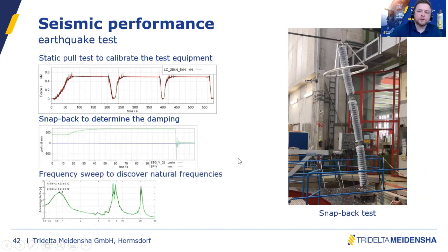And then, as you might see in the picture, the surge arrestor is placed on a so-called shaking table, a big hydraulic table, which can apply a certain acceleration, ground acceleration, to the surge arrestor. And with that table, we are shaking in different directions with different accelerations, and we can go from a very low frequency to a higher frequency.